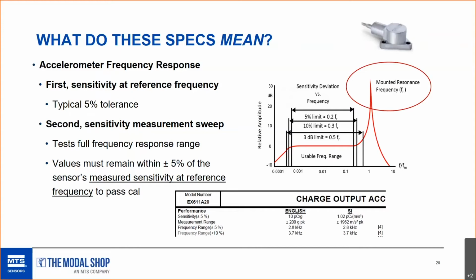If you get a picocoulomb output, if you want it to be in G level, you need to know the sensitivity. And what we see here is a sensitivity in picocoulombs per G or picocoulomb per PSI, measured at a reference frequency. 100 hertz, in my language, that's 6000 cycles per minute, right, Mike? So you'll see the frequency expressed in different terms, either in units of hertz or CPM.